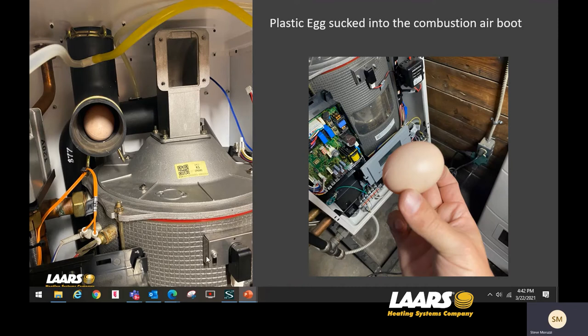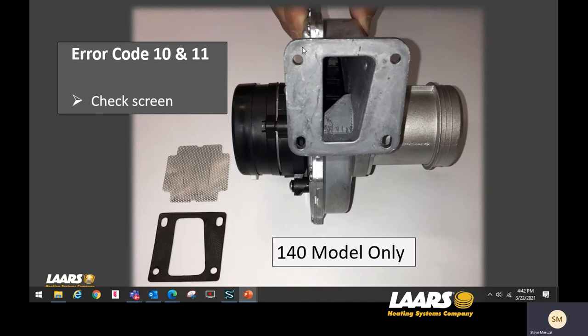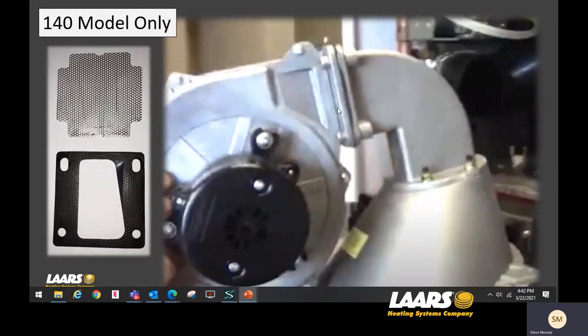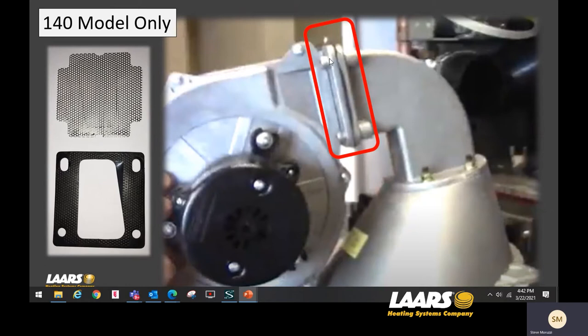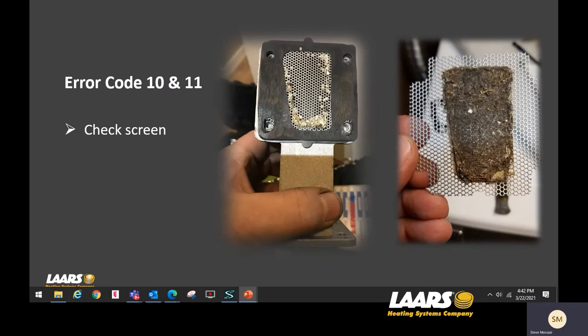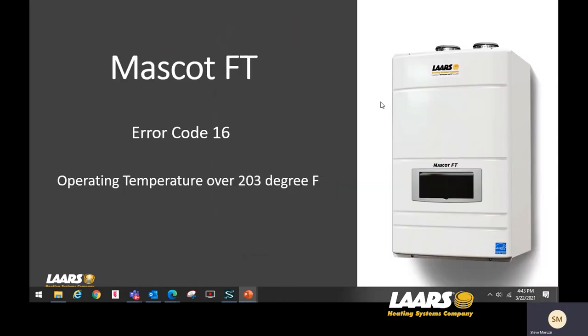Error codes 10 and 11 on the 140 models — there is a screen on the outlet side of the blower where a lot of debris gets caught. That screen is located right between the blower and the burner arm; you'll have to remove the nuts and bolts to gain access. We have found all kinds of things: PVC shavings, dryer lint, bugs, and grass clippings. All of those things can plug up your burner or the screen on the 140 models.